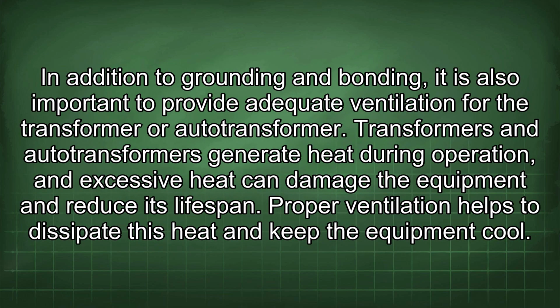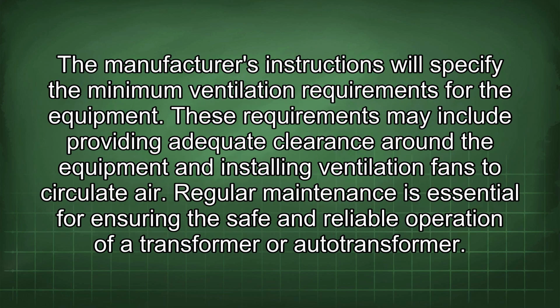In addition to grounding and bonding, it is also important to provide adequate ventilation for the transformer or autotransformer. Transformers and autotransformers generate heat during operation, and excessive heat can damage the equipment and reduce its lifespan. Proper ventilation helps to dissipate this heat and keep the equipment cool. The manufacturer's instructions will specify the minimum ventilation requirements for the equipment. These requirements may include providing adequate clearance around the equipment and installing ventilation fans to circulate air.